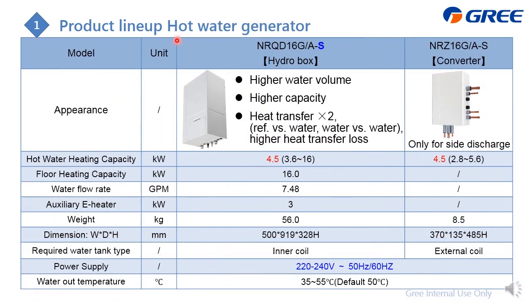Next we will go to the hot water generator. For this one we have two types, which are the hydro box and the converter. And I will analyze the difference here for you. First, from this model you can find that they can both produce hot water, but the working theory is different. For the hydro box there are two stages of heat transfer. First is from the refrigerant to the water, and then we use this hot water to heat up the water again. That means two stages. But for the converter we just use the refrigerant to heat up the water directly.